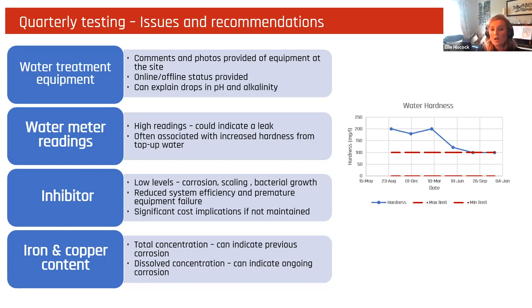We had another network that was flagging high levels of water hardness, and when we monitored this against other parameters, it was found that there were also falling levels of inhibitor. When this was flagged with the maintenance contractor, who had been redosing the system, it pointed towards the potential for a leak. We recommended that they install a water meter on the makeup water, and this became part of our monitoring to flag how much was being added to the system.